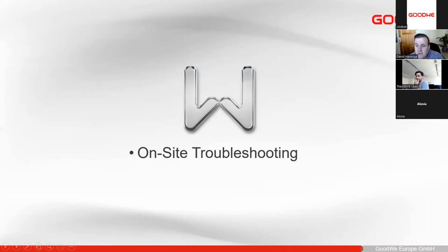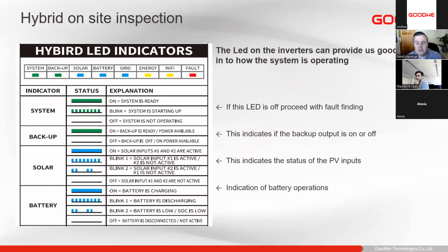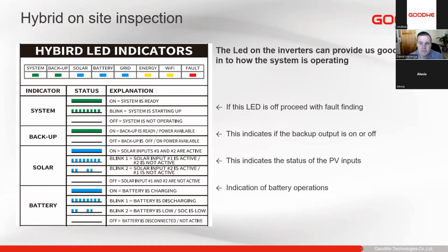The next is the on-site troubleshooting. So if you do go on site, or if the end user is on site and they say they're experiencing a problem, the first place one can look is the LEDs on the inverter. Please always reference the side of the inverter, where you'll always find the reference code for what the LEDs indicate on the inverter itself, or you can look at the user manual, which is also available on our website.